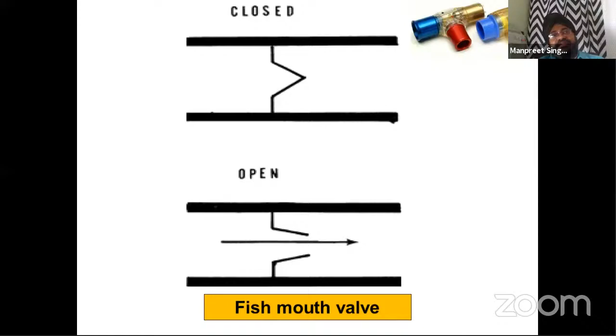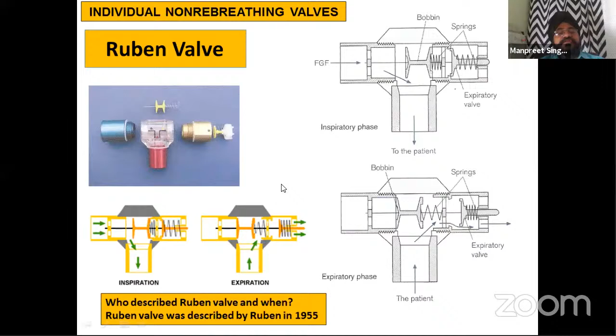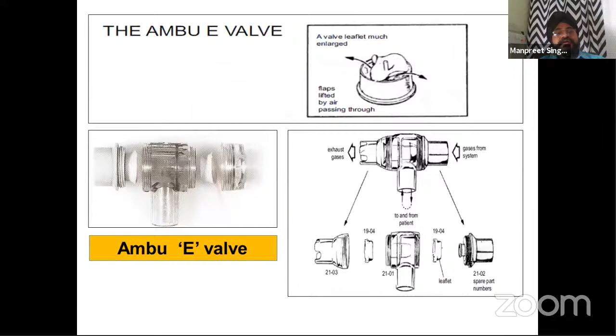It is an individual non-rebreathing valve. You can see that this valve was most commonly used earlier. It has a bobbin in the center with the spring, and when the fresh gas flow goes in, this bobbin moves back and the spring moves back, and the air goes inside to the patient. This is the inspiratory phase. When there is an expiratory phase, when the patient exhales, this bobbin comes back, the spring is back, and then from the sides it exhales. So this is the Ruben valve. And you know, the Ruben valve was described by Ruben in 1955.